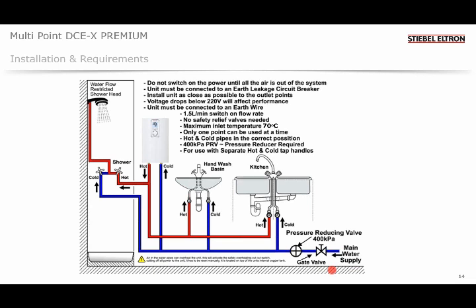We do recommend having separate hot and cold tap handles. Part of it is that if it's a low quality mixer with a lever, you might have issues where you have leakage from the cold water, even if it's just on hot, and then you might have issues with the unit. Also be aware that, as the cold water is split, going cold and also through the unit itself, you will have pressure losses through the instant water heater, and you just need to balance accordingly for that.